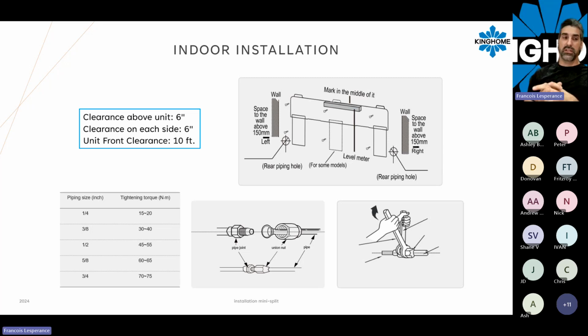Also, in front of the unit, because the blower motor is quite strong, we have a good throw for the air supply on these units. We need a minimum clearance of 10 feet just in front of the unit, because if it's less than that, sometimes you can take in the same air again and run into performance issues or maybe short cycling, which we want to avoid. Again, we have a flare connection behind that head, so the torque wrench on your flare connection is pretty important. Make sure you will not face a leak a year after.